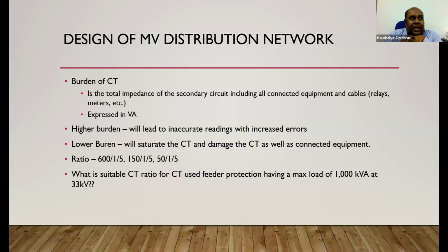Yes, what are the ratios that we employ? This is a very crucial thing. Can someone tell me the most suitable ratio for a CT for a feeder having a load of 1000 kVA at 33 kV? The current shall be nearly 18 amperes. If you are using a 600 to 1 CT, how fair is that? If you are using a 150 to 1 CT, how fair is that? If you are using a 50 to 1 CT, how fair is that?